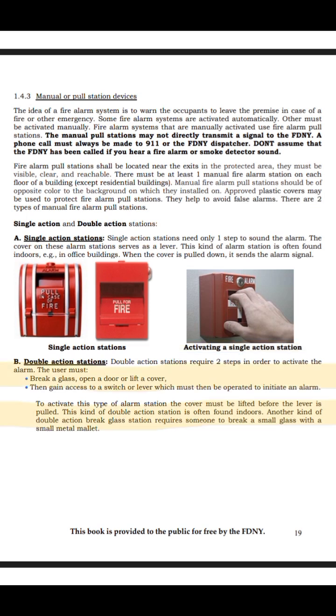Double action stations require two steps. In order to activate the alarm, the user must break a glass, open a door, or lift a cover, then gain access to a switch or lever which must then be operated to initiate an alarm. To activate this type of alarm station, the cover must be lifted before the lever is pulled.